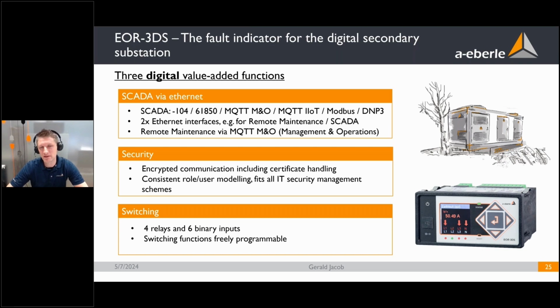The one is for maintenance, so for firmware updates and parameter updates. The second one, the IIoT, is more to have all this data on a second network for other departments like asset management. The device has 2 Ethernet interfaces on the back and also one with an adapter on the front. So in total, we even have the possibility of 3 Ethernet interfaces, but 2 are available on the back, for example, if you want to have different networks for remote maintenance and SCADA communication. And as said before, the remote maintenance is especially available via the management and operations protocol, which I will explain later on.